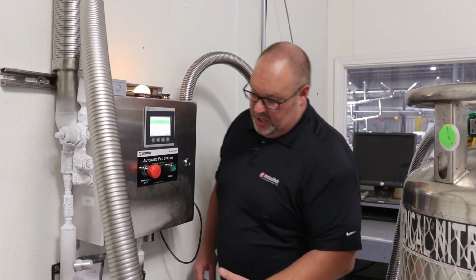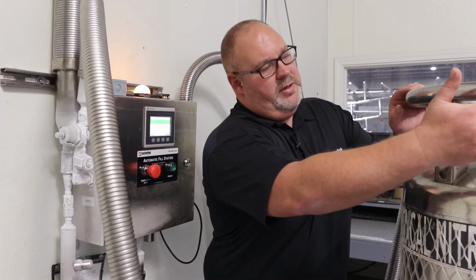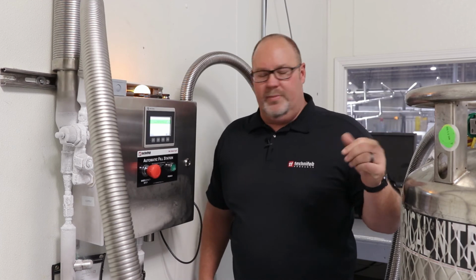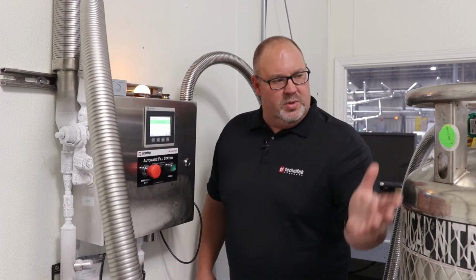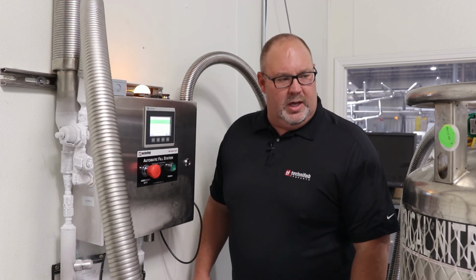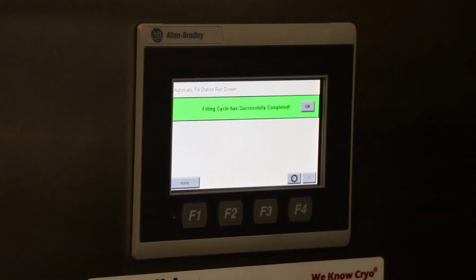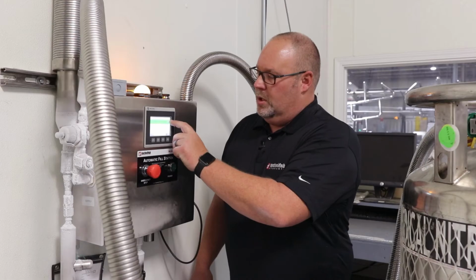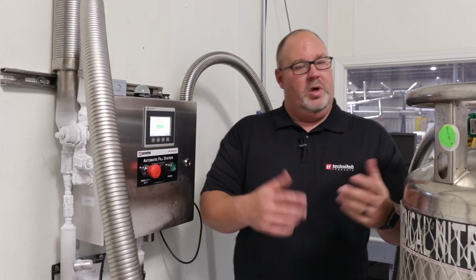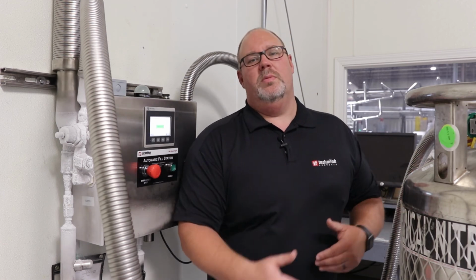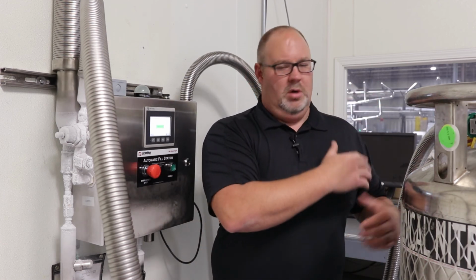OK. So at this point in time, we would undo our transfer hoses from the dewar, both sides. There, you would still see some frosting and some things like that occurring with the lines. You'll also still see some cryogenic vapors that would expel from the lines once this is completed. So your filling cycle is successfully completed. You hit OK. And then what you would again do is bring in your next dewar, hook up your supply line, hook up your vent line, and start the process all over again.